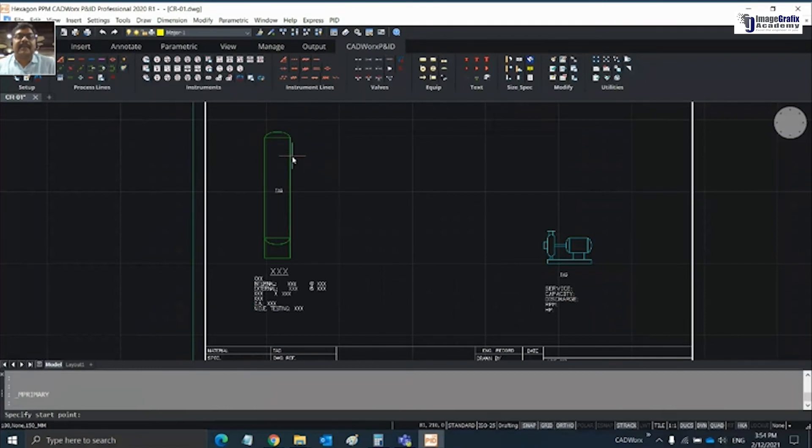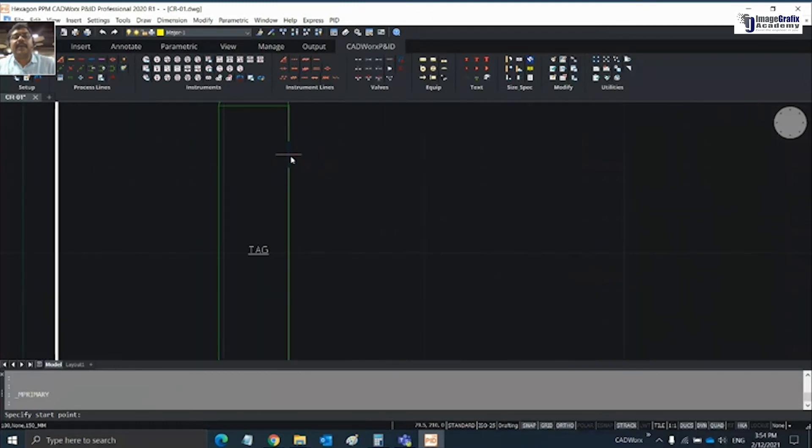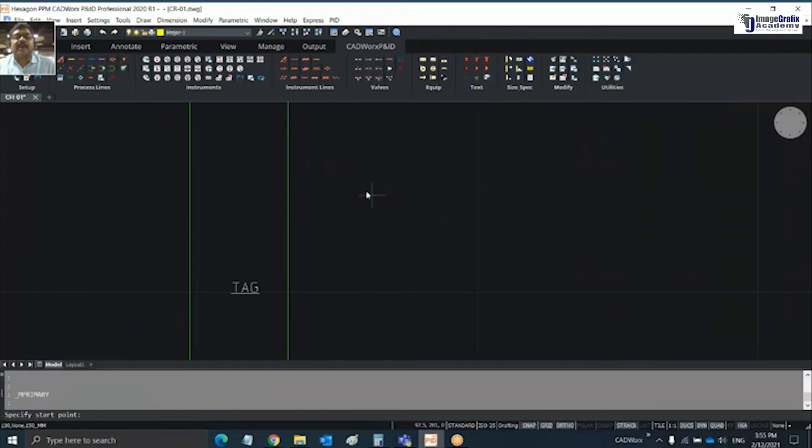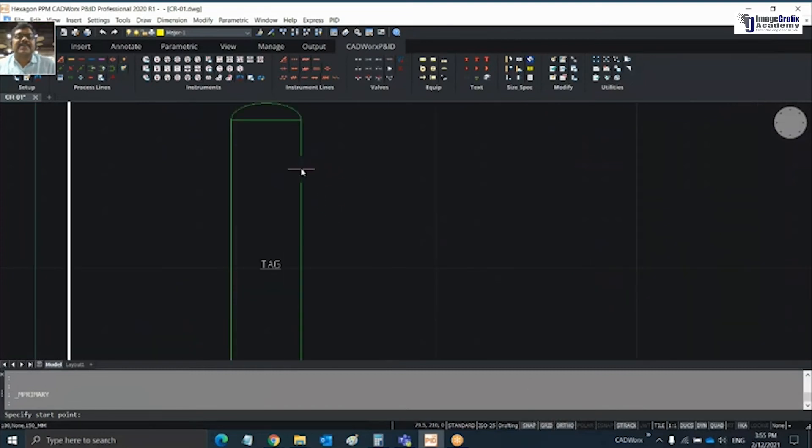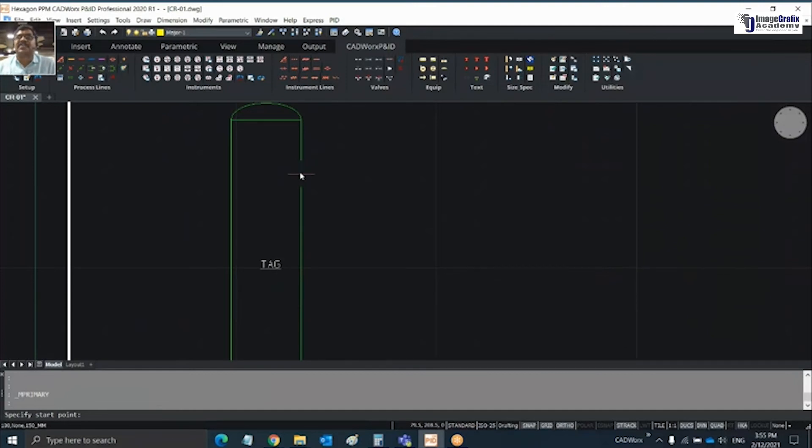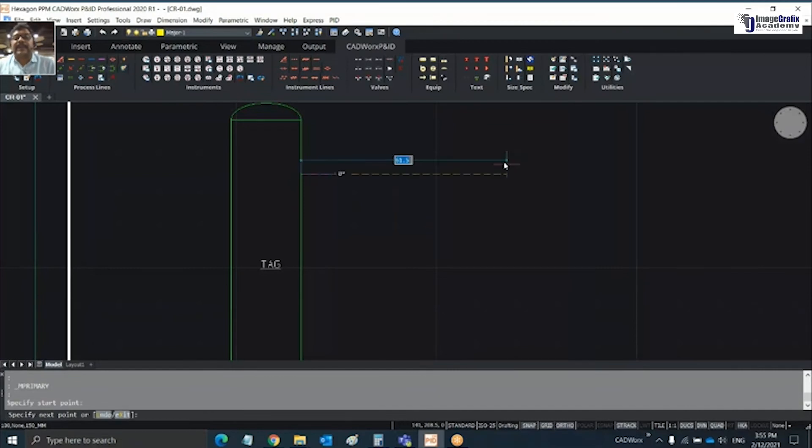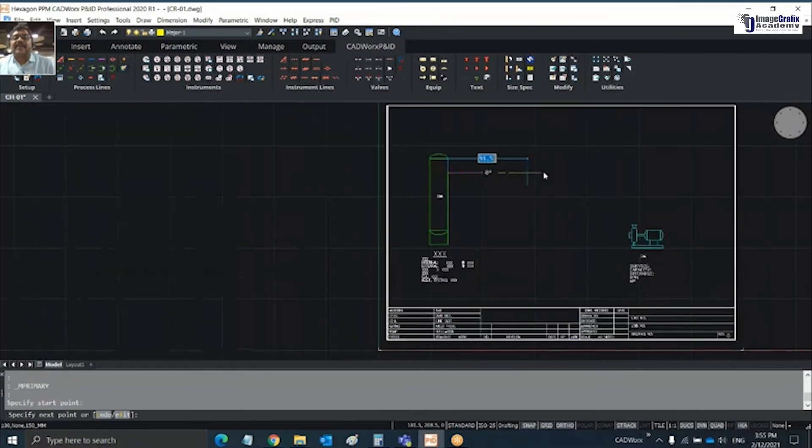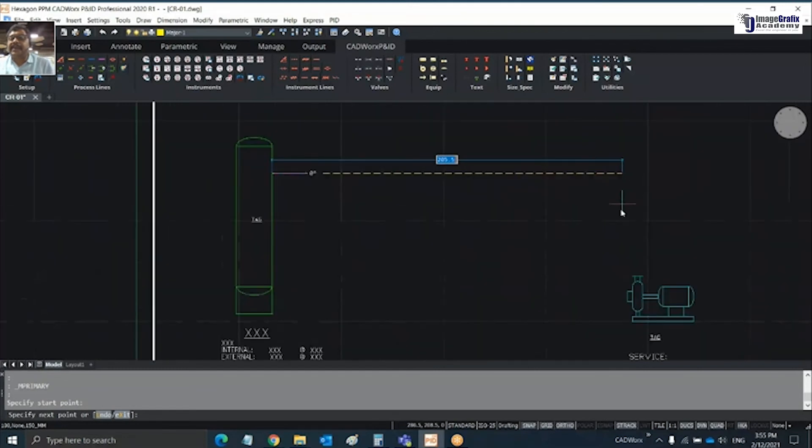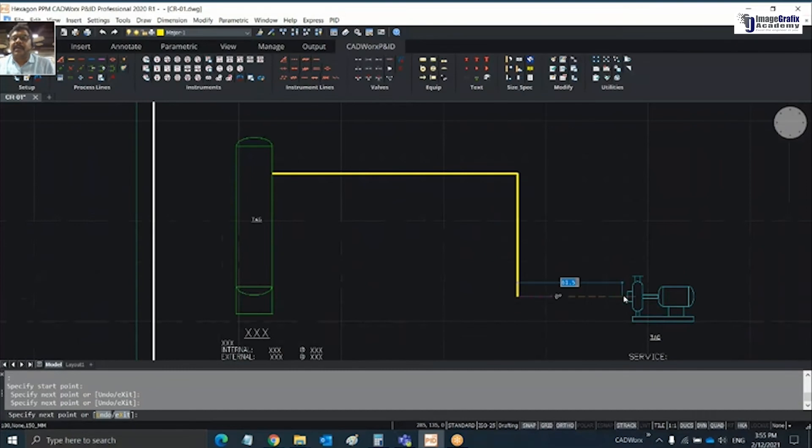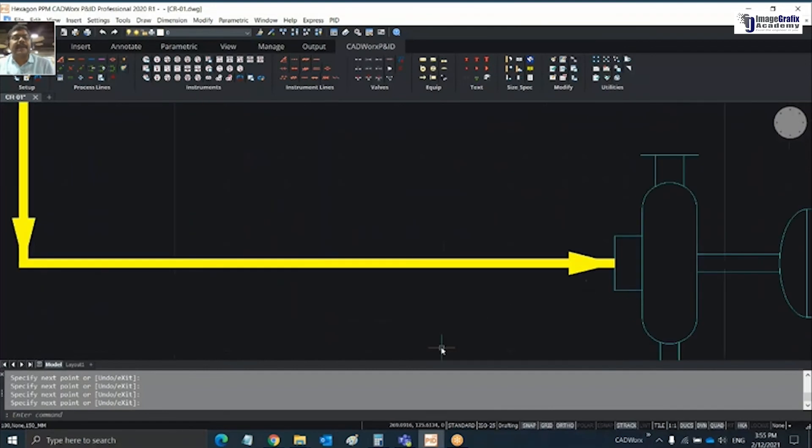Once this is set, next I'm creating a process line. By default in P&ID, make sure that your snap, grid, and ortho is turned on because that will simplify your drawing creation process. When you move your cursor, it sticks to the object from where you want to start. Now I'm starting this line from here and connecting it to this, joining to this and here. You can see it automatically places the arrows and your process line is ready.